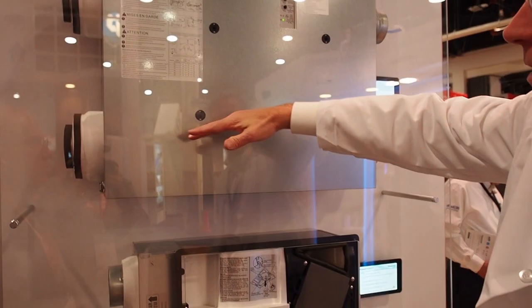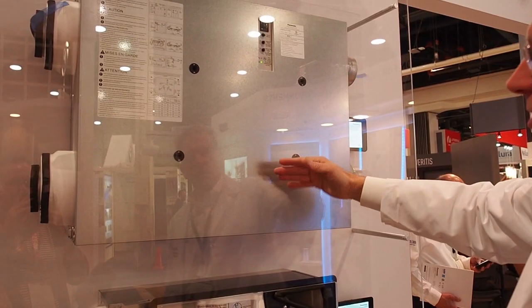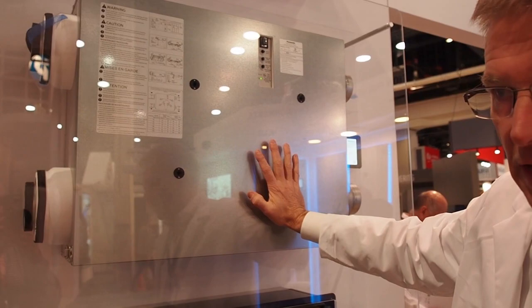DC motors up here, this runs at about 54 watts which is pretty remarkable. Pretty low energy. Again supply air is going to come through here, it's going to go through a core exchanger and be exhausted out in the house. Exhaust air from the house is going to come through here and drive it out of the house here.